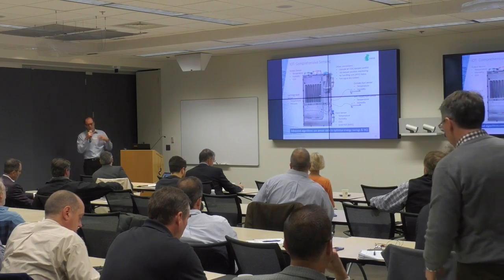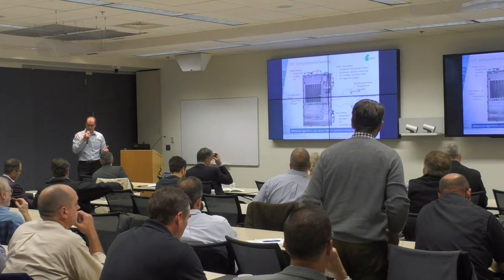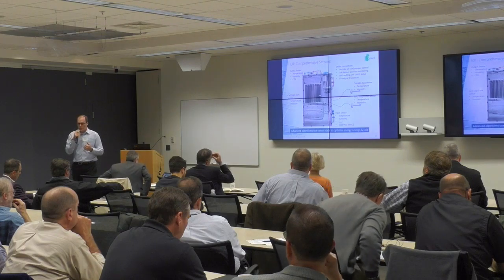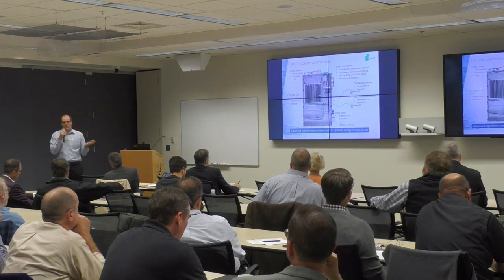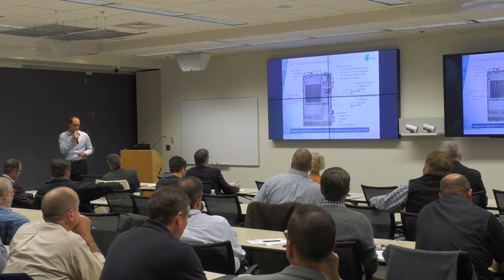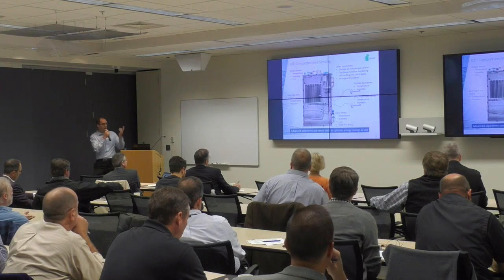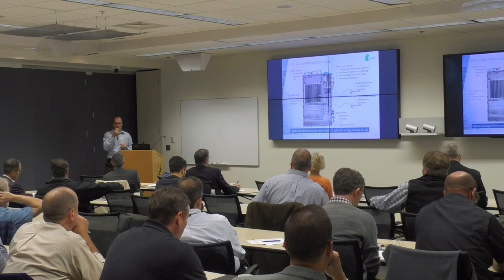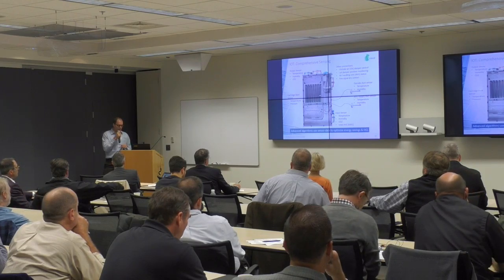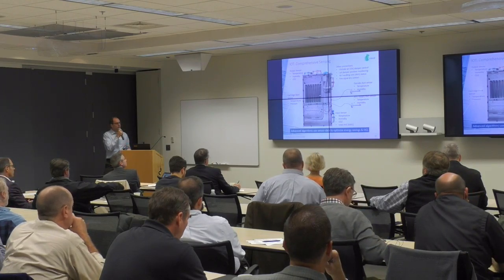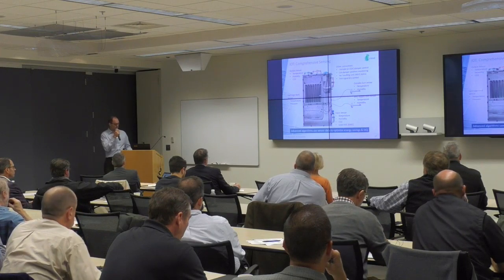These sensors help us determine when we should be cleaning the air, when we should do a regeneration, when we should just be in idle mode, and when the building should go into economizer mode, where you want outside air to come in. So there's pretty sophisticated software associated with this.